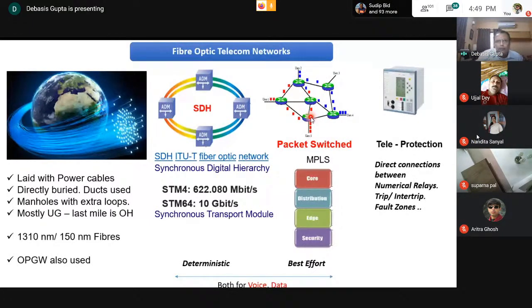The third widely used aspect of fiber is tele-protection. You have these numerical relays, line differential, distance relays. They all use fiber point to point for tripping and intertripping, and for defining those zones, zone 1, zone 2, zone 3, which trip and which don't.